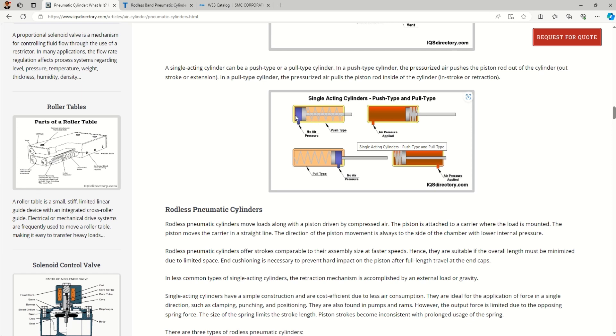In a push type cylinder, the home condition has the rod at the return stroke and the spring is on the rod side. When you supply air to the piston side, the piston compresses the spring and moves forward — giving the forward stroke. So in push type, we are pushing the piston against the spring, and the retracted position is the home position.